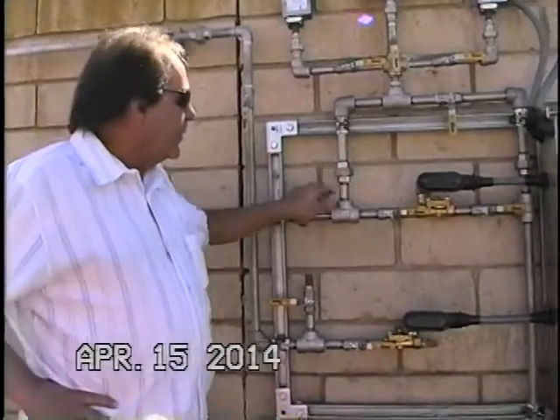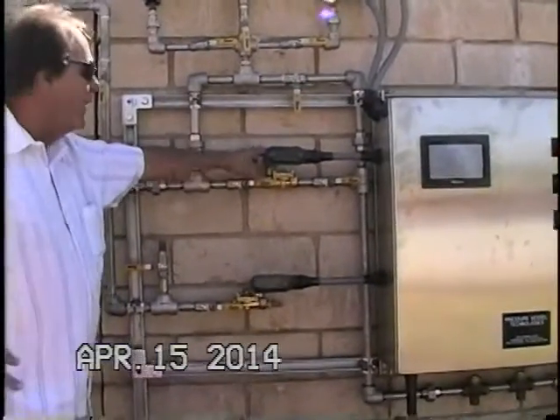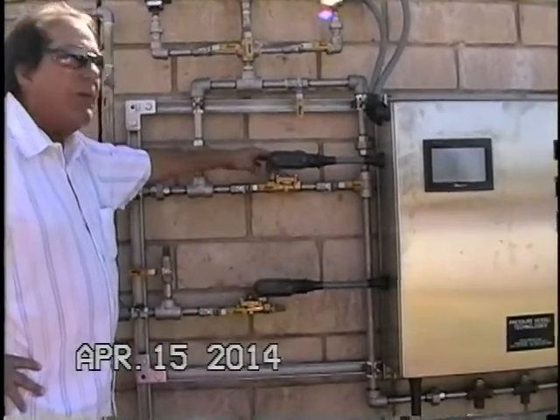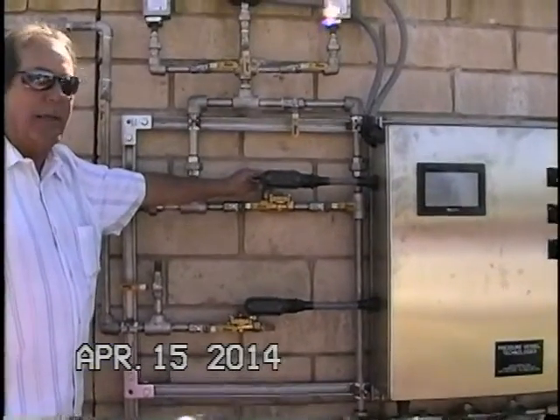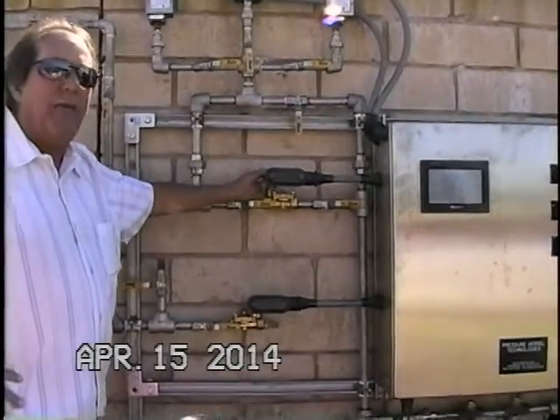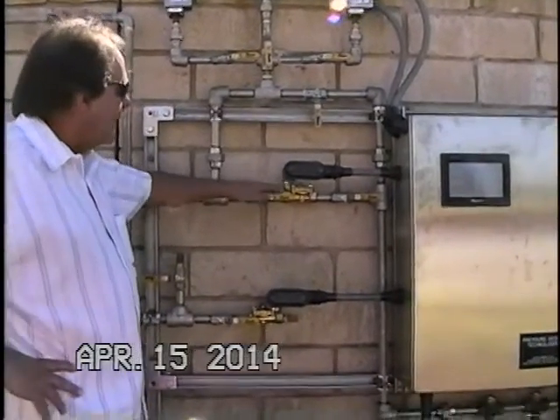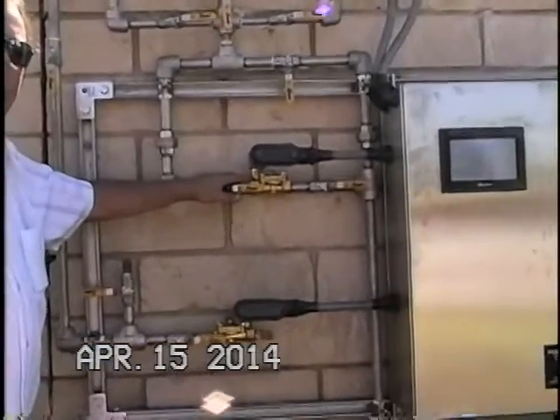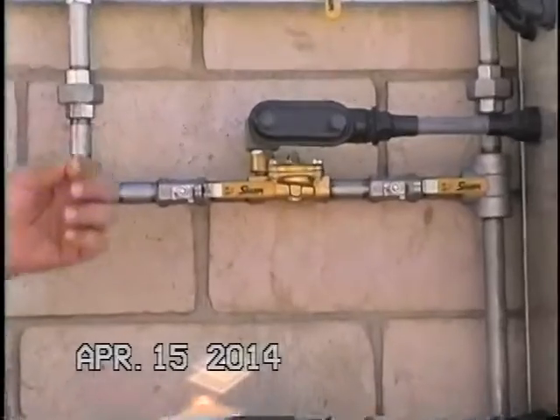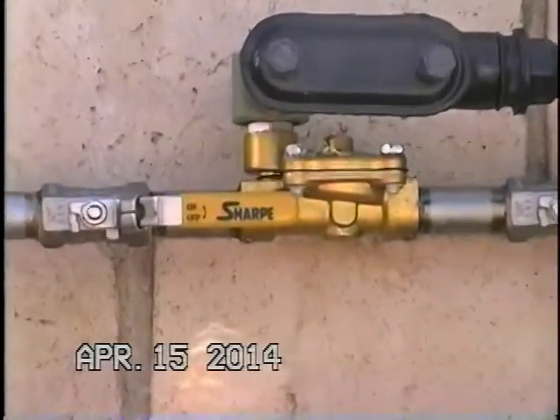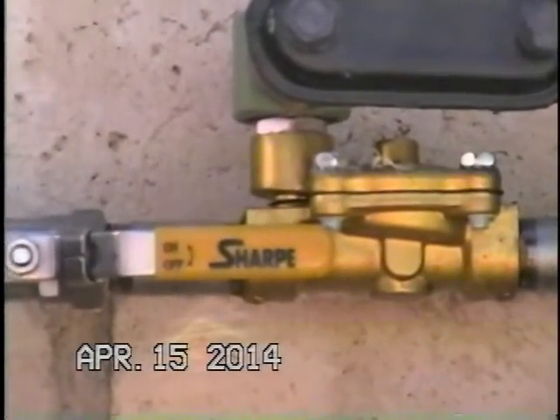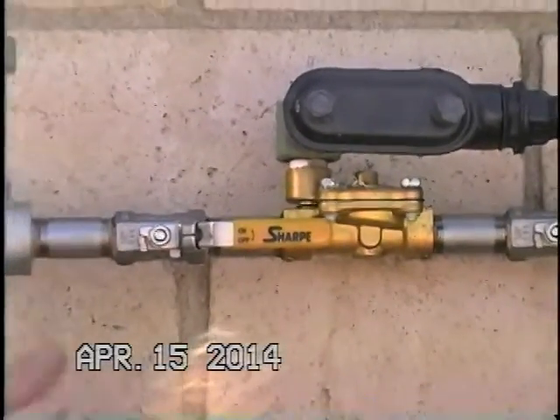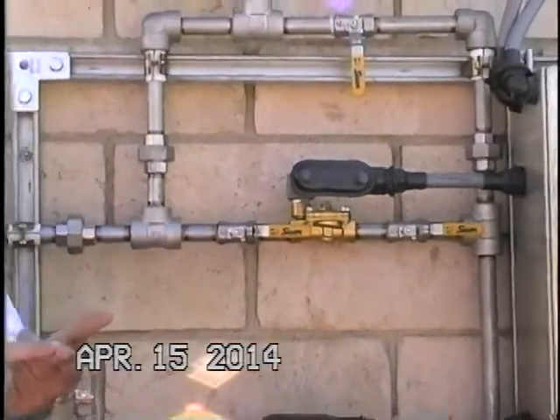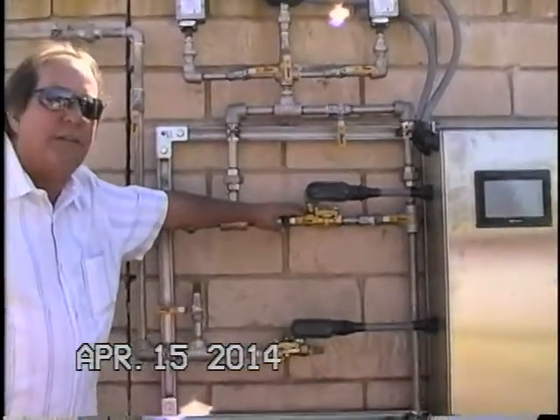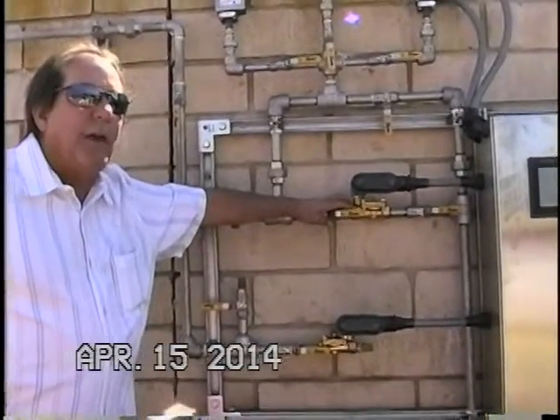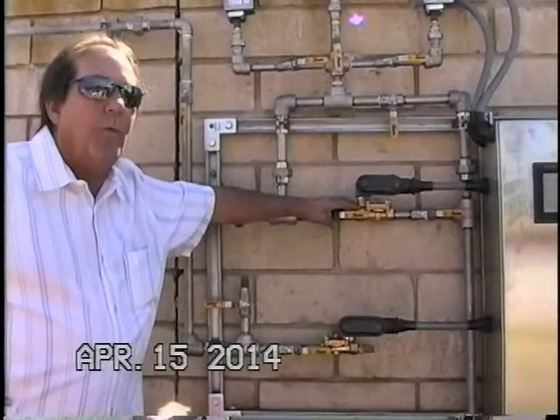We have 2 solenoid valves. These are ASCO solenoid valves. They require very little maintenance, if any. The only condition I've ever seen in a new system is that they're actuated by a small needle valve on the inside, a small actuator point inside that valve. If a little pebble gets into the air line, or a little piece of Teflon tape, it's possible that it could get stuck. The only time we've really seen a failure of these valves is probably because of one of those two conditions.